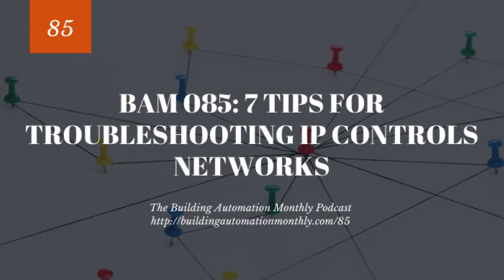And that would make things to where your traffic can communicate and not fall off into the middle of the earth. But until that happens, that's something you need to be aware of, because if you start to see time-based traffic losses, time-based communication losses, where it's like, every night at midnight I lose communication to the BAS. Well, I wonder why that is. Oh, there's database backups going on at that time.